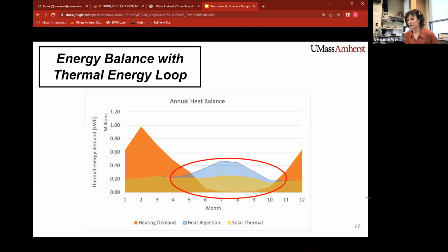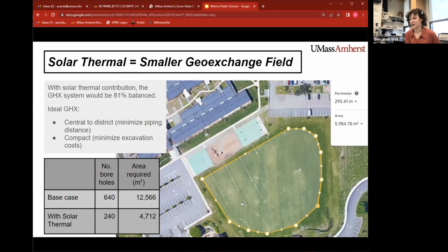With the addition of solar thermal, this is what the heat balance model for the proposed system looks like. With solar thermal contribution, the ground source heat exchange system would be about 81% balanced, meaning the system can be downsized by about 62%, going from 640 boreholes down to 240.